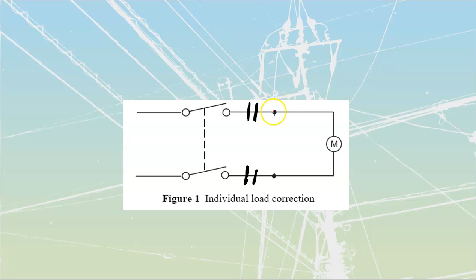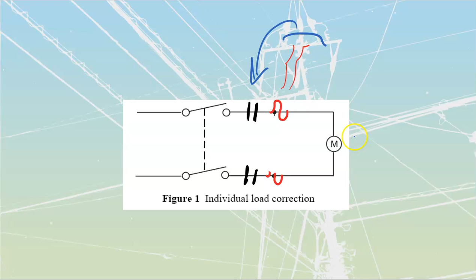You should have had those explained to you inside of first year as well. But motor overloads are simply going to be current responsive devices. Downstream of my contactor, my current goes through. Here's my disconnect switch. Here's my contactor. And then it's going to go through this set of overloads over here. And what these overloads are designed to do is heat up based upon motor current. And if they get too hot, they're going to trigger a little bimetallic strip that's going to be inside of my control circuit. That bimetallic strip is going to be tied into my controls to open this set of contacts, basically shut it down.